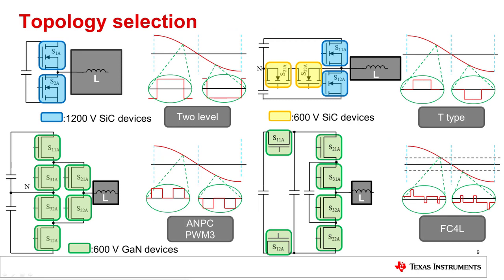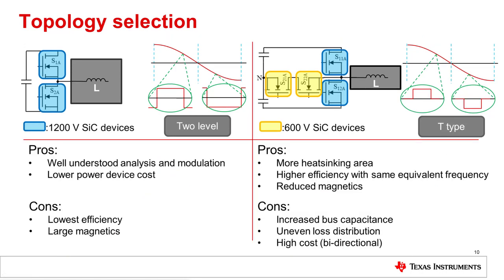To determine the best topology for a 5-kilowatt grid tie converter, several topologies were analyzed. For 1200-volt devices like silicon carbide MOSFETs, the two-level and T-type topologies were investigated. For 600-volt GaN devices, the three-level ANPC and four-level flying capacitor topologies were investigated. The two-level topology has the advantages of simple control and the minimum number of devices, and the half-bridge design and control is well understood. By looking at the circuit schematic, it would seem to be the best topology — but why are many PV inverters adopting the T-type topology instead?